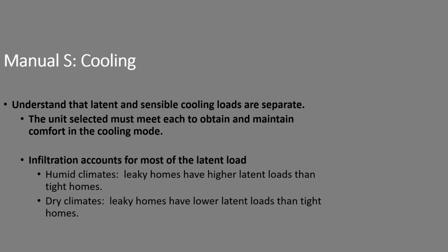Manual S cooling, understand those two loads are separate. Again, what's interesting is in other parts of the country, if you have a leaky house, the latent load increases because of all the humidity outside. In dry climates like ours, that leaky home, actually the air is so dry that the leakiness actually dries it out further. There are 4 important things to remember when sizing for cooling. Once again, we live in the great Northwest where we don't have to worry about dehumidification. That's the good news. Air conditioning originally meant you have to reduce the latent load and the sensible load.